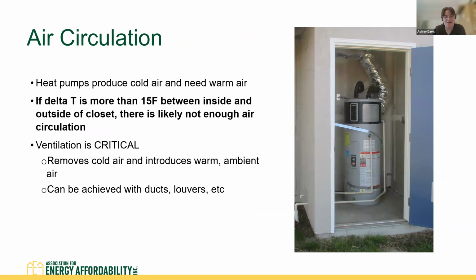So the biggest thing, honestly, that you have to think about when thinking about unitary heat pump water heating design is circulation, right? As Ari said, a heat pump removes heat from the outside air, puts it into the water. That means you're left with a bunch of cold air. So your heat pump is, when it's running, continuously exhausting cold air and continuously needing more warm ambient air. And we found that if the temperature difference between the inside of the heat pump water heating enclosure and the outside of the enclosure is more than about 15 degrees Fahrenheit, there's probably not enough air circulation.